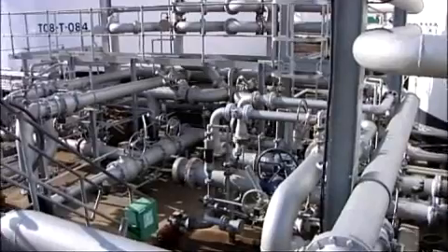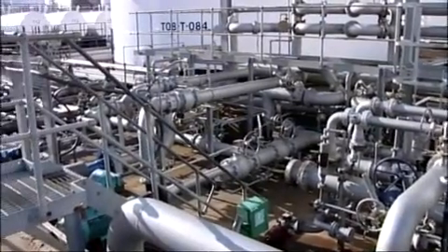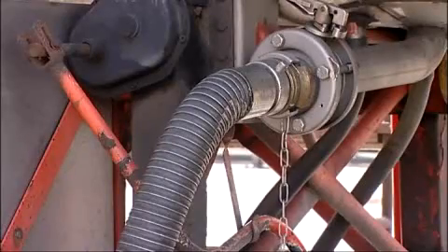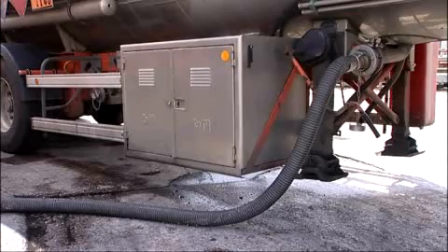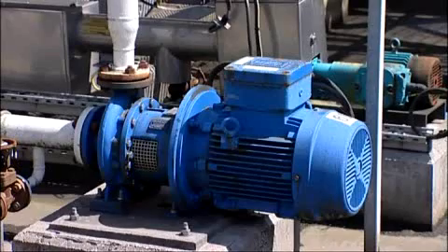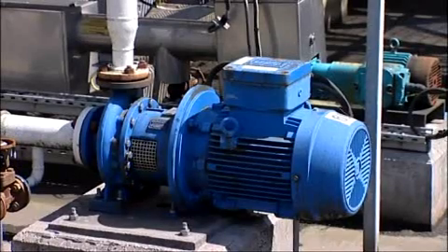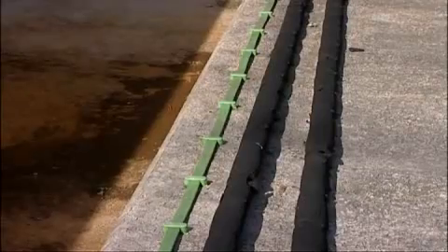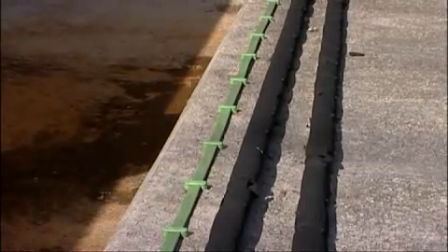In potentially flammable locations, all conductive objects electrically isolated from earth by non-conductors, such as non-conducting pipe or hoses, flexible connections, equipment supports, gaskets, should be bonded. Bonding straps and cables and earthing bars should be durable and low resistance, of less than 10 ohms.